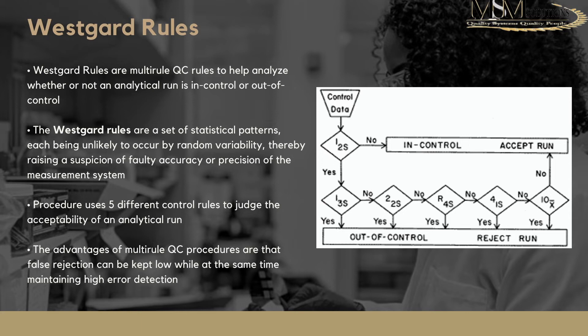This procedure uses five different control rules to judge the acceptability of an analytical run. The advantage of using a multi-rule QC procedure is that false rejections are kept to a minimum while still maintaining a high error detection system. When you read your QC results, the first question you ask is: is this value outside my 2s limit? If no, it's within control and you can accept the results.